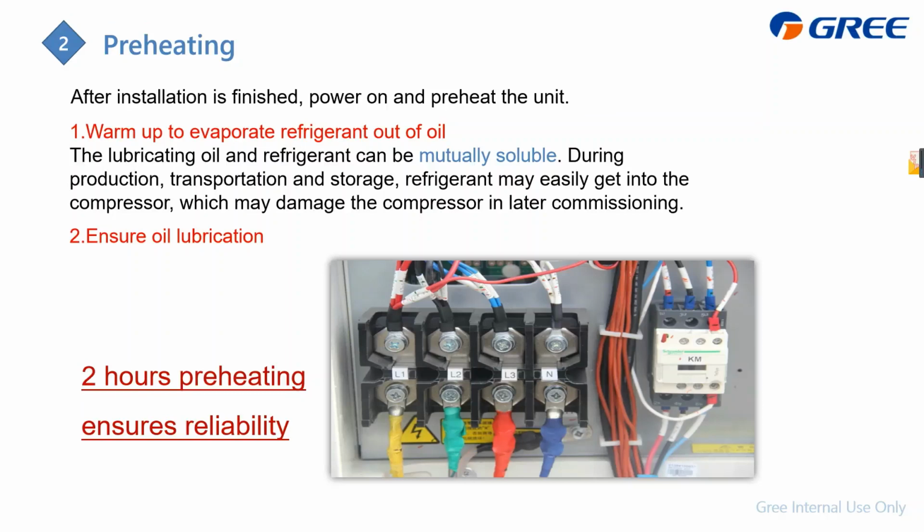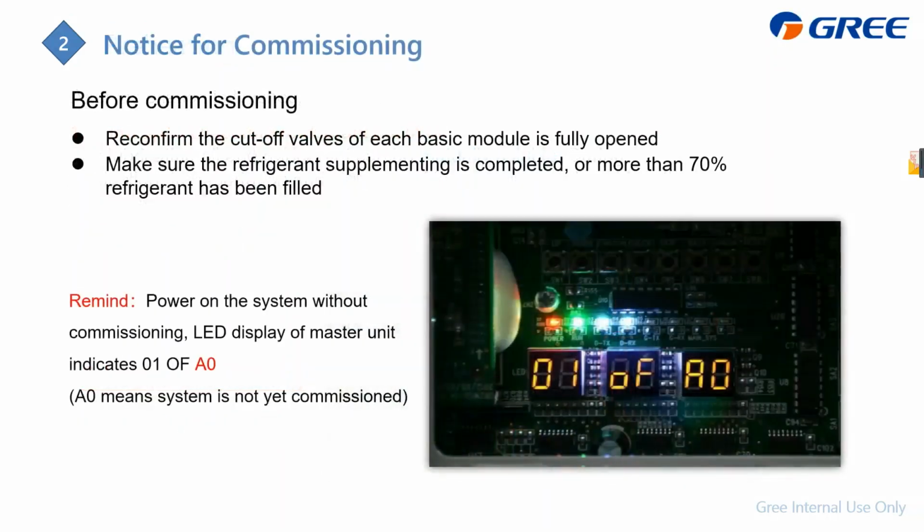So we should preheat 2 hours for our GMV 6. And before commissioning, the mainboard will display 01 OF A0.